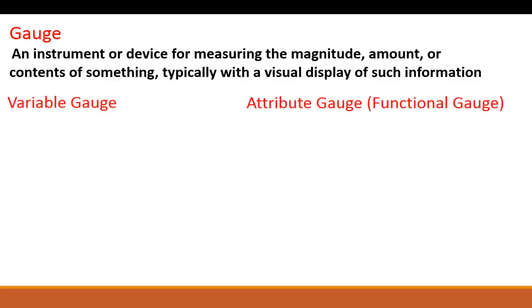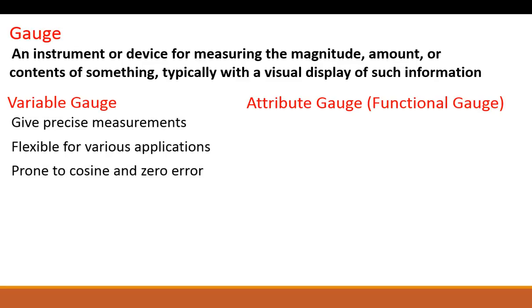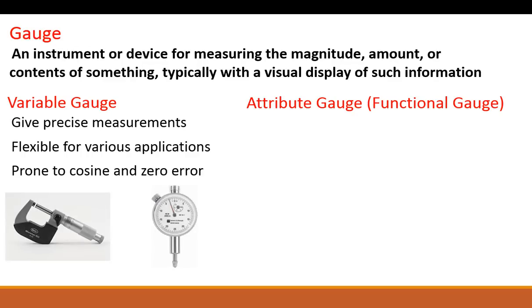As far as inspection, we have two different types of gauges: a variable gauge and an attribute gauge, also known as a functional gauge. Variable gauges give precise measurements — they're flexible and have a lot of different applications. You can take a variable gauge and measure several different types of features and components. However, they are prone to certain types of errors, two of which are a cosine error and a zero error.